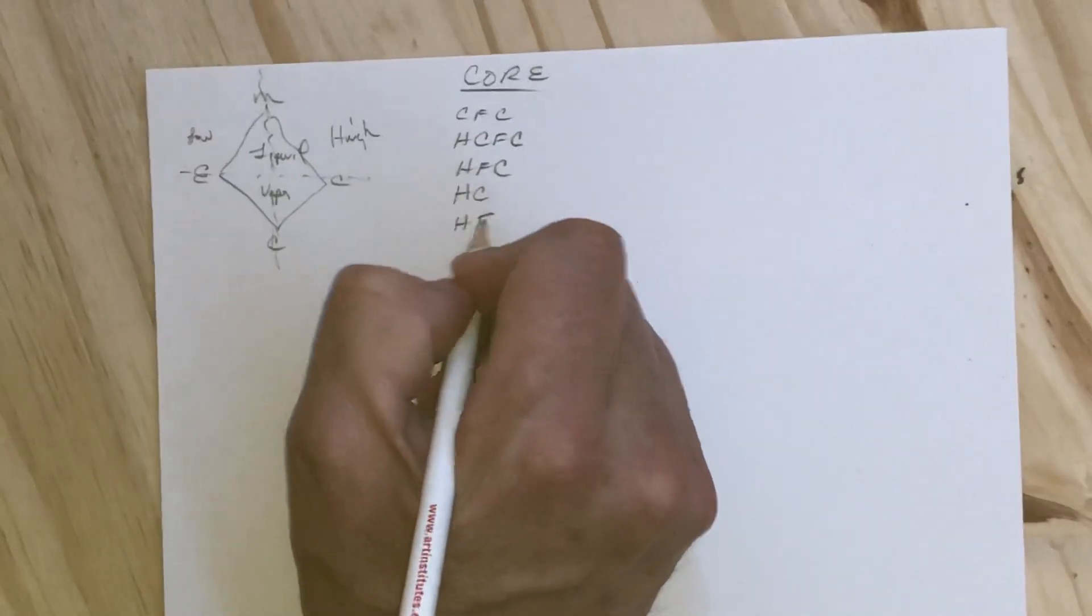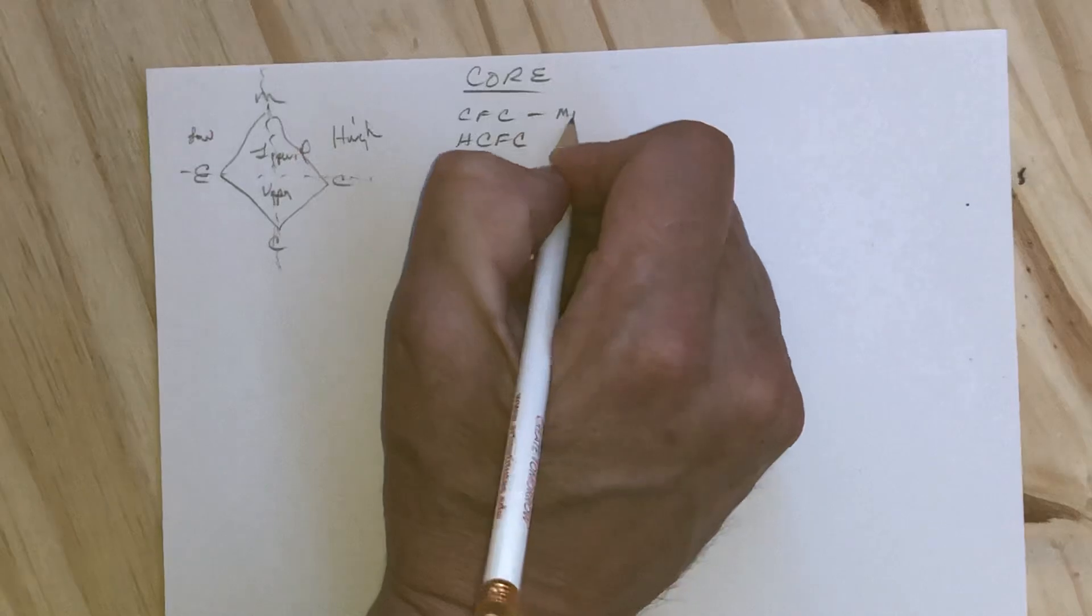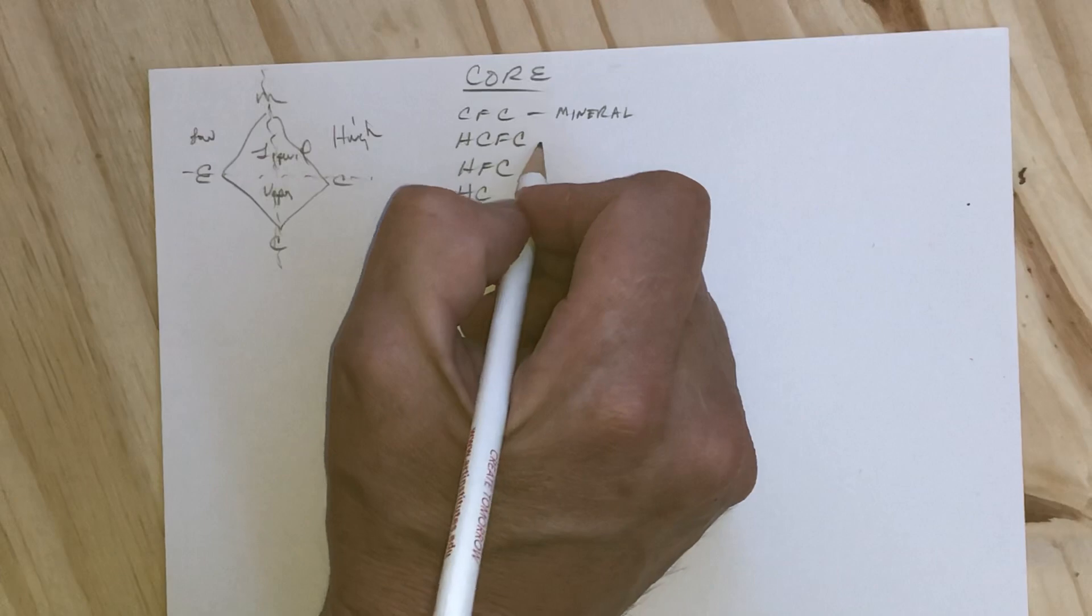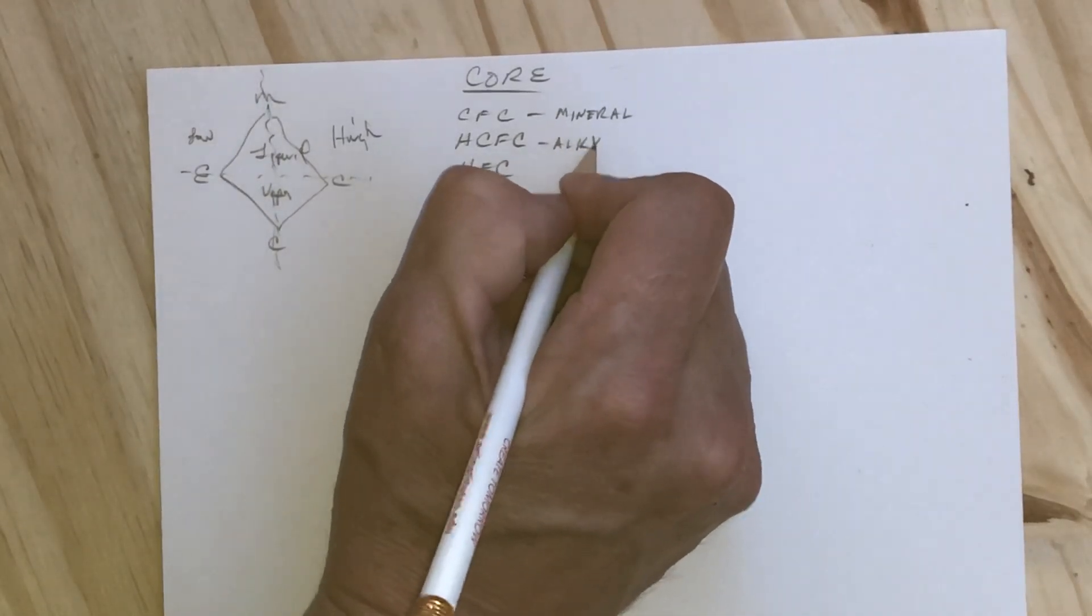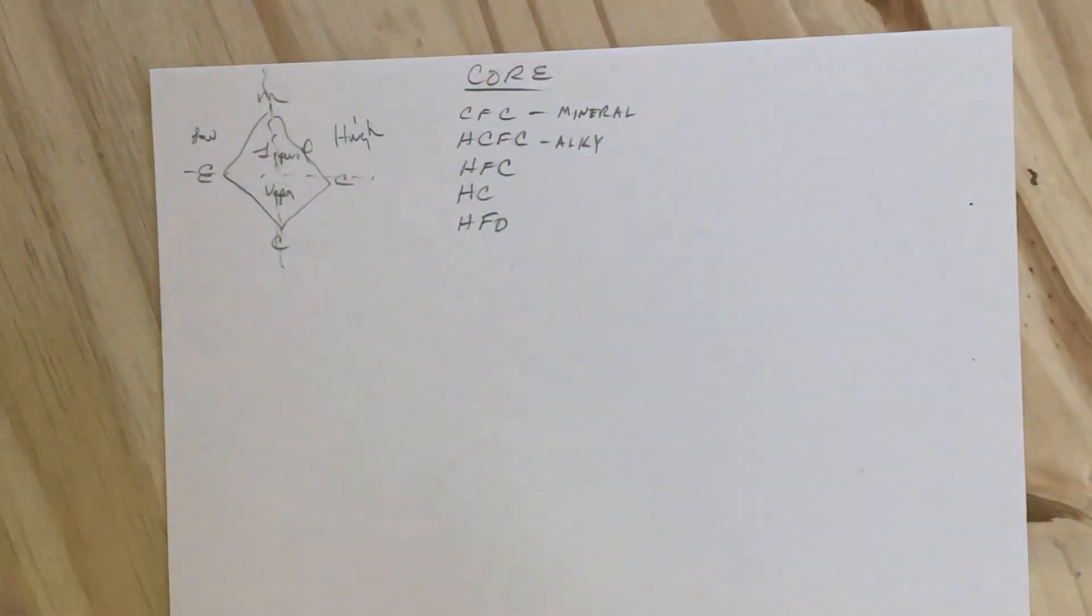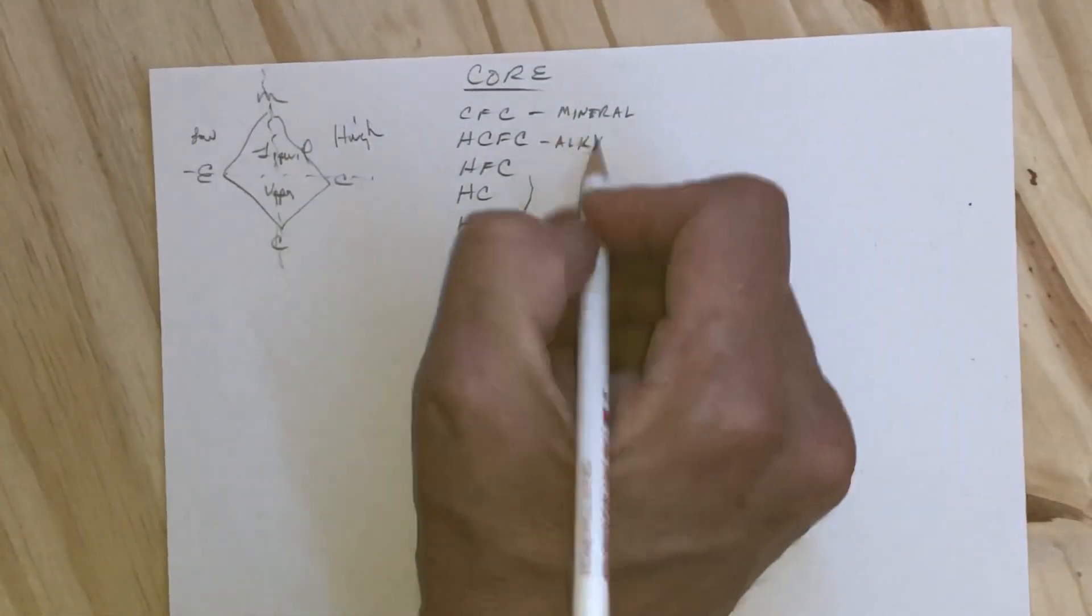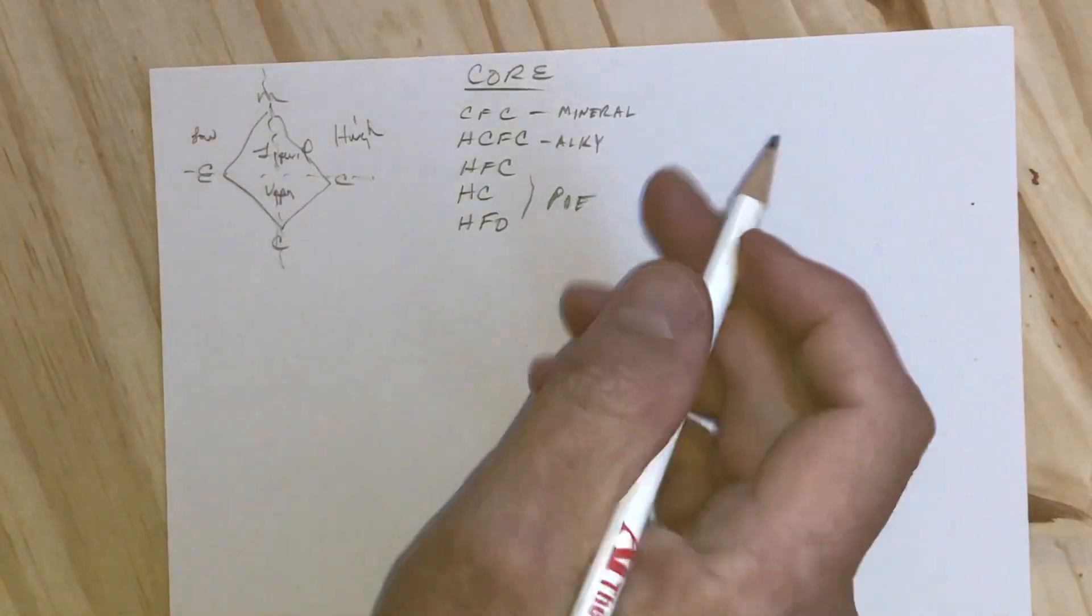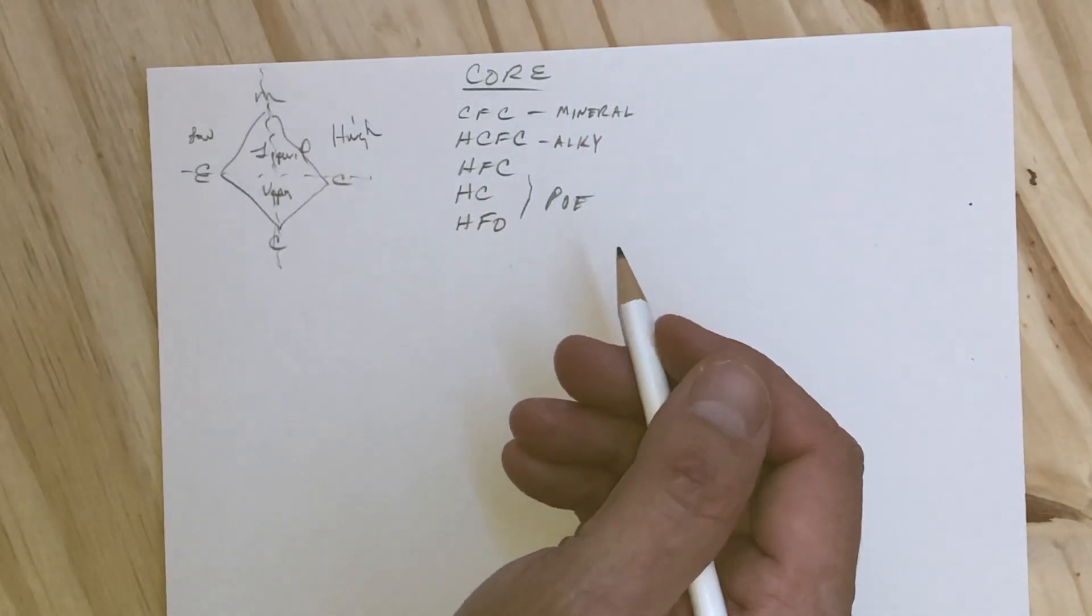With these refrigerants come their oils. Mineral is used primarily for chlorofluorocarbons and R-22, but R-22 could also use alkylbenzene with the rest of the HCFCs. These in here all use the polyester oils.